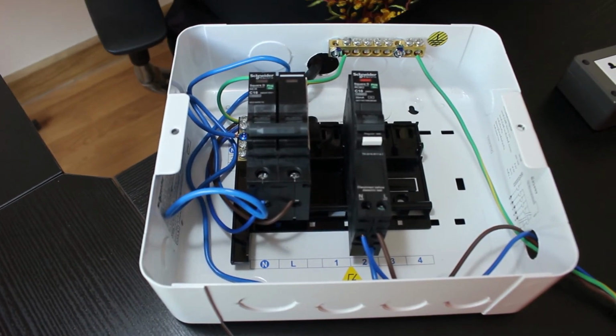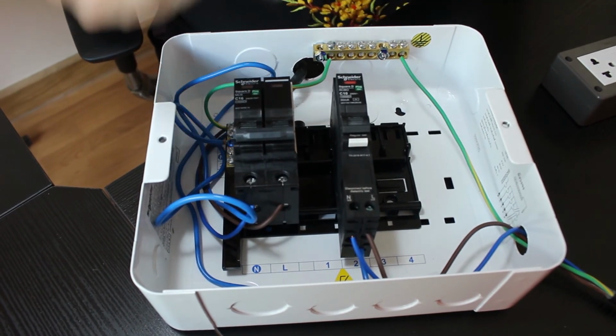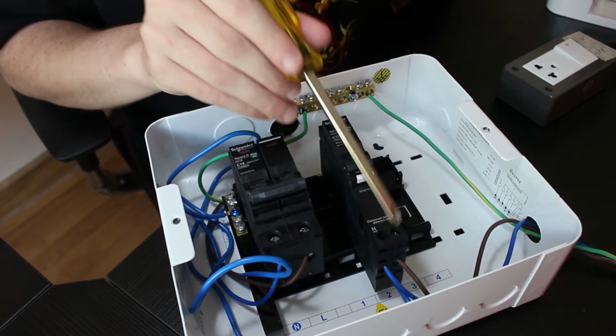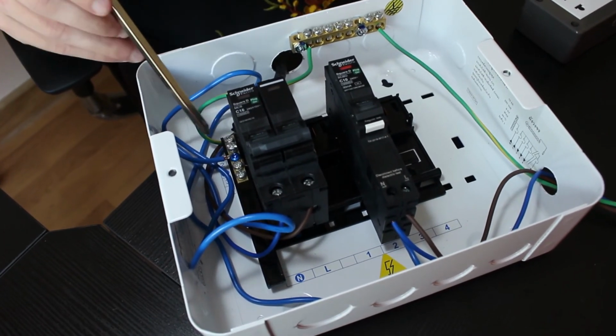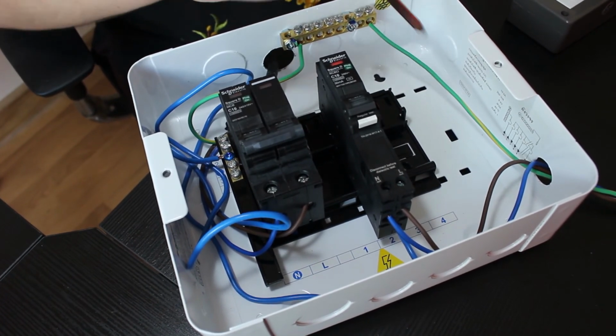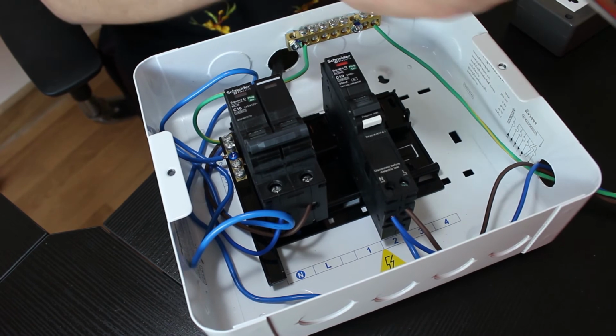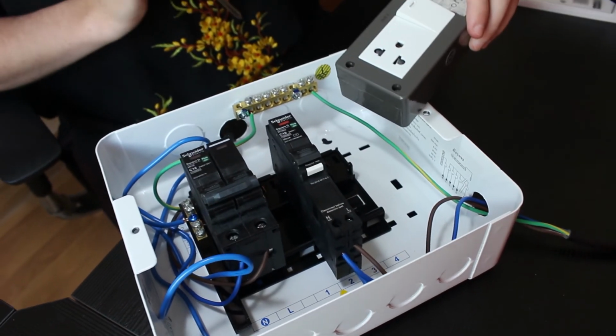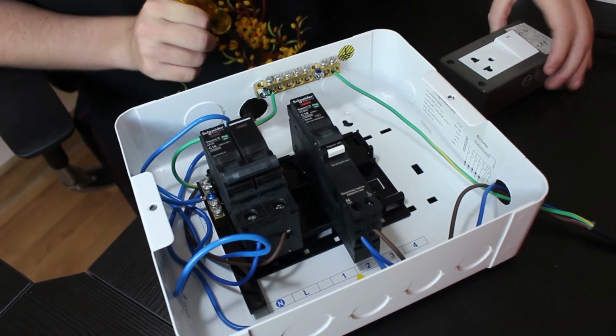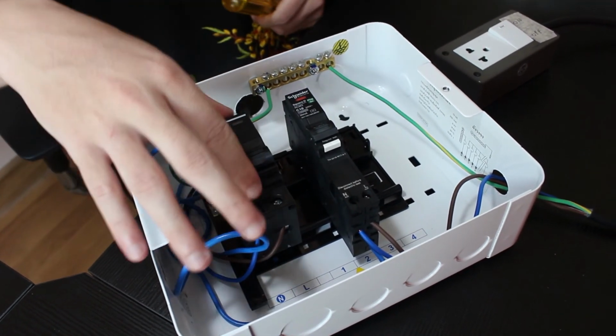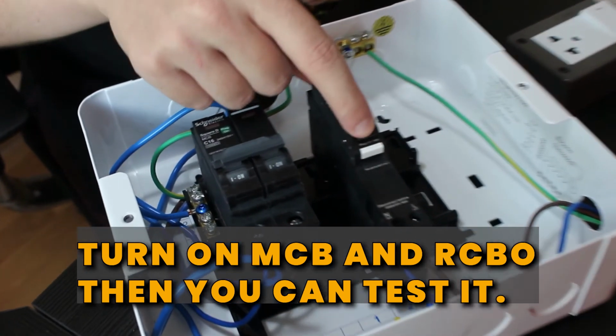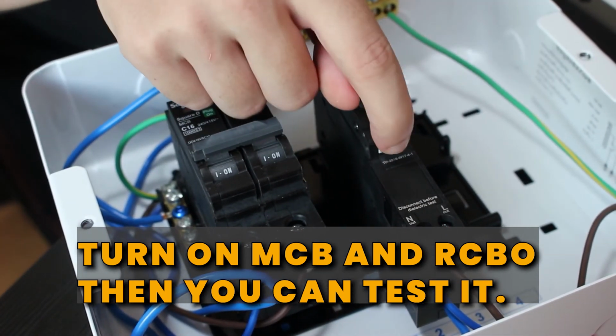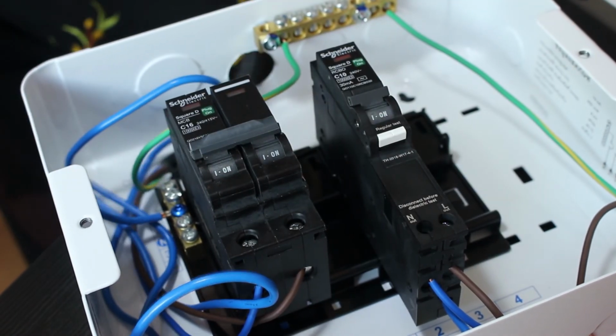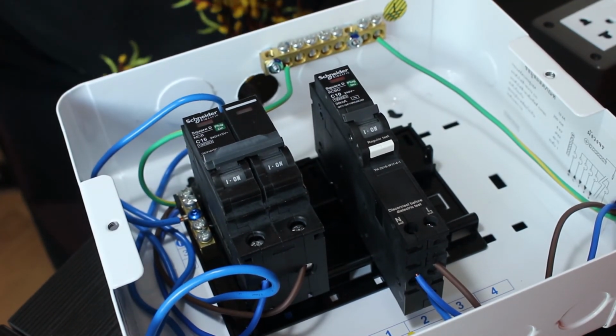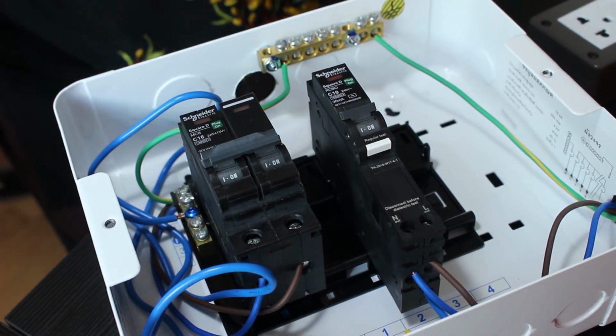The RCBO itself needs a little bit more wiring because you need to measure the differential. So you're going to have the line out, the neutral out, and you need to add another neutral that goes onto the neutral bar here. After that, you just have to wire the earth, line out and neutral out from the RCBO to the plug that you want to use to connect your electronics, and you should be good to go. Every time you start it up, you're going to have to turn on the MCB, turn on the RCBO, and you can test it. Here it's not going to trigger because we are not connected in any way. Do not do those kinds of modifications with the system under power.